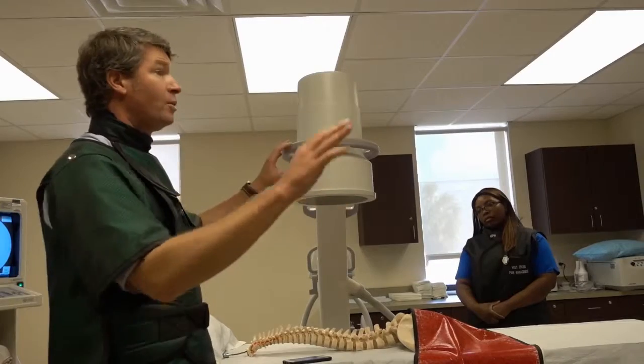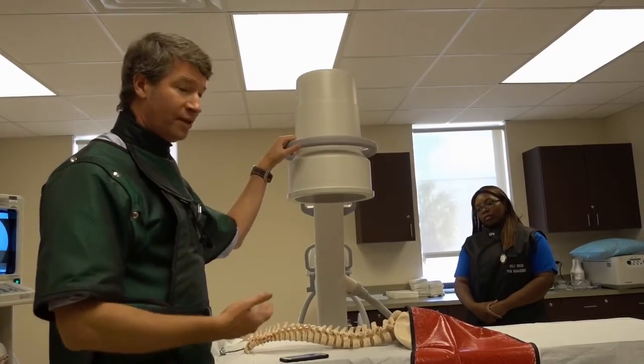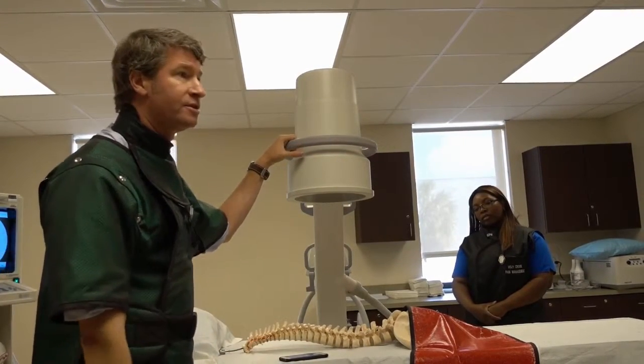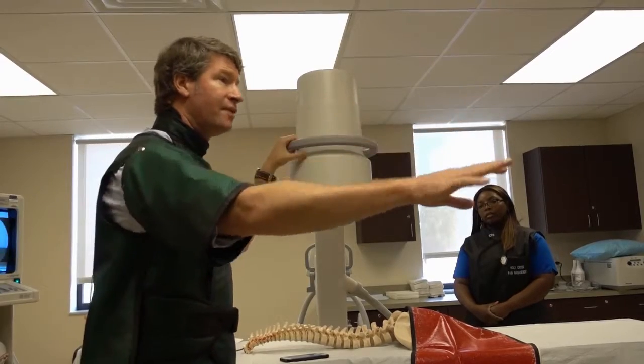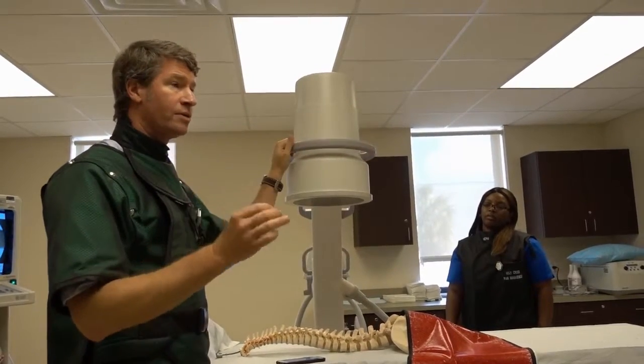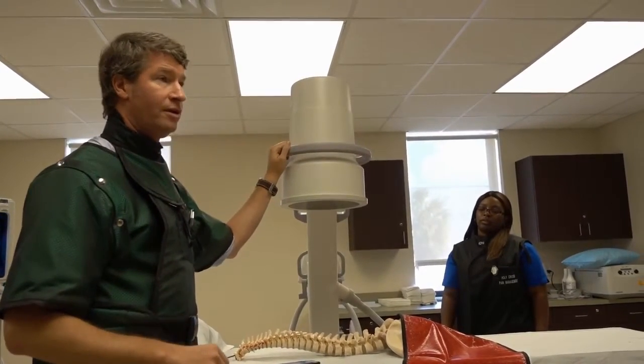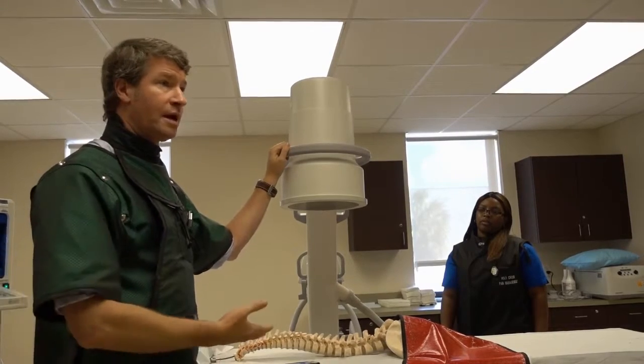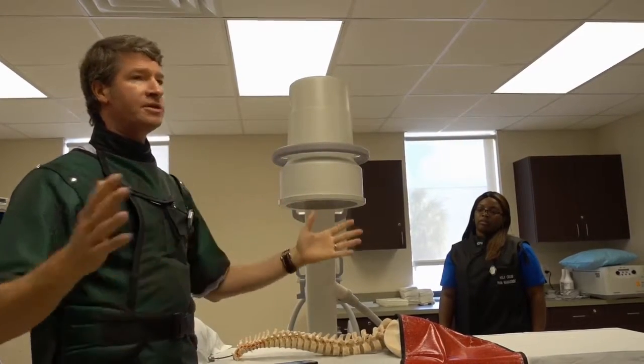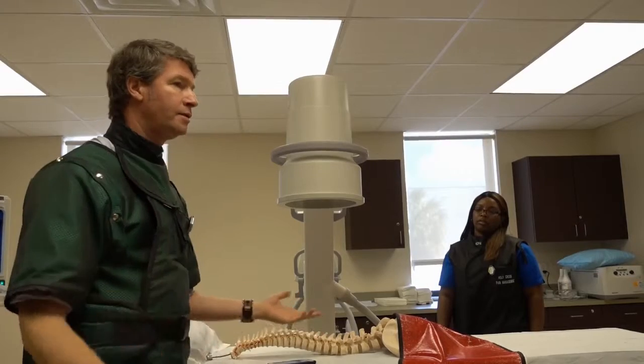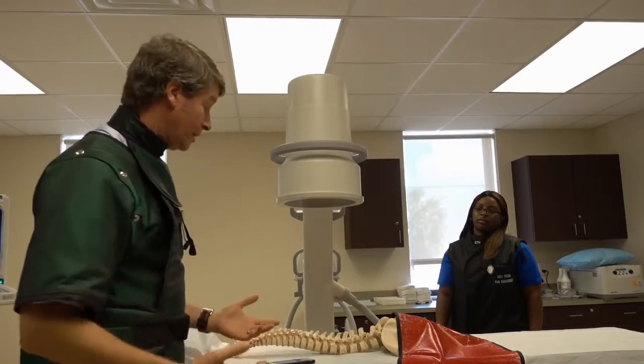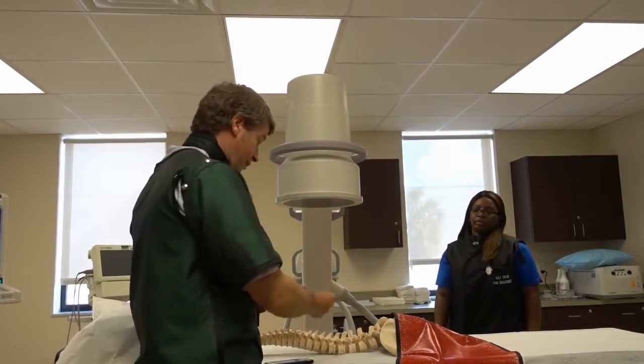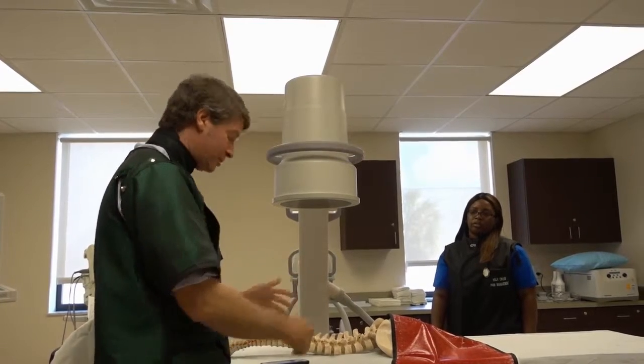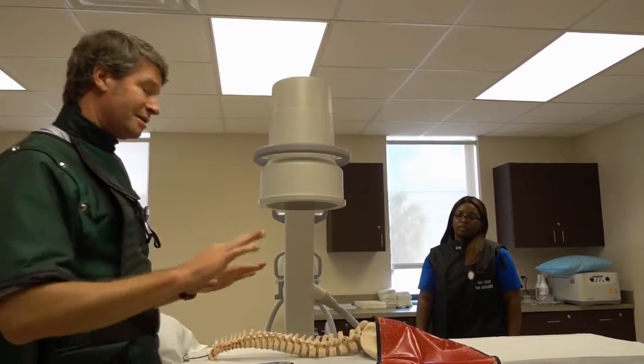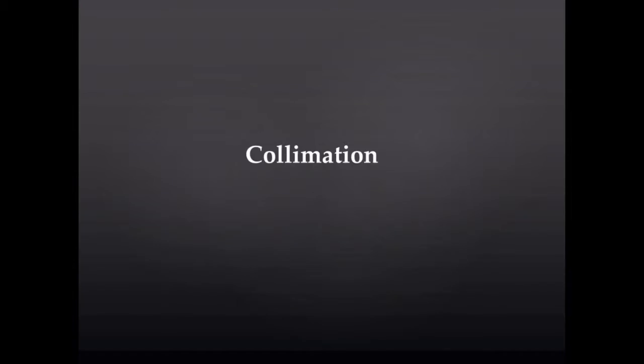And that's why we don't have a lead-lined building. We don't have a lead-lined floor. The people downstairs are safe. The people upstairs, the people outside are safe. At 6 feet, it's equal to the same radiation you would get from standing in the sun with it constantly on. So it drops precipitously down. So if someone's walking through, they don't need lead. If you're in the corner, you don't need lead. But if you're here, you need lead. And if you're here, you really need lead unless you're the patient. So distance is king.